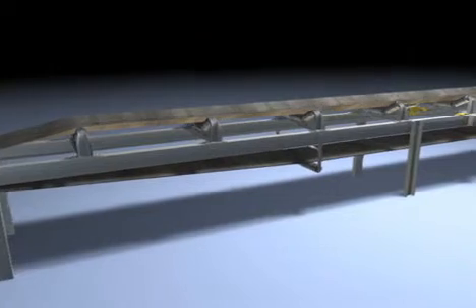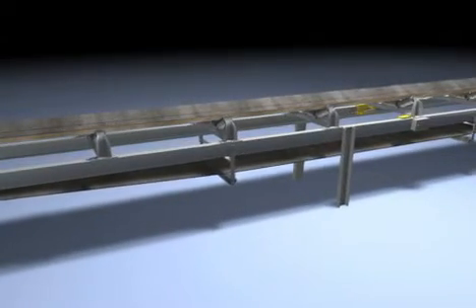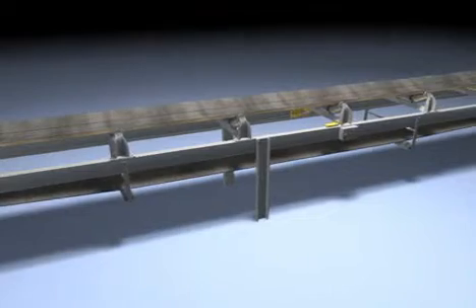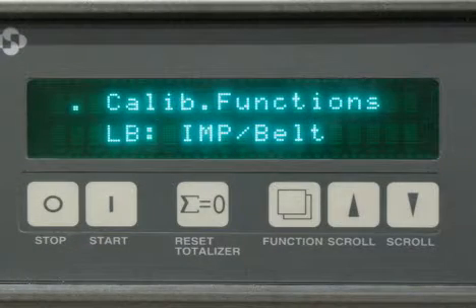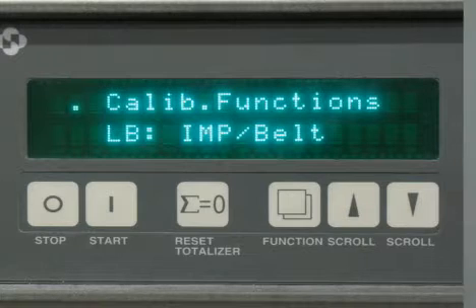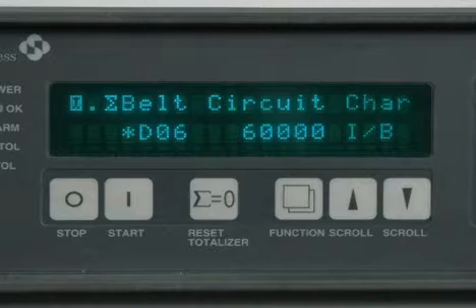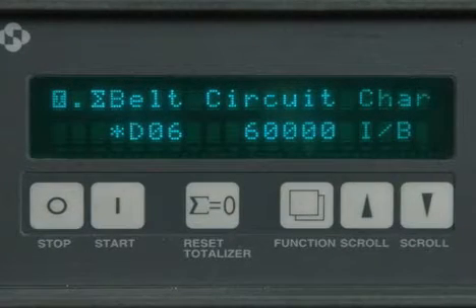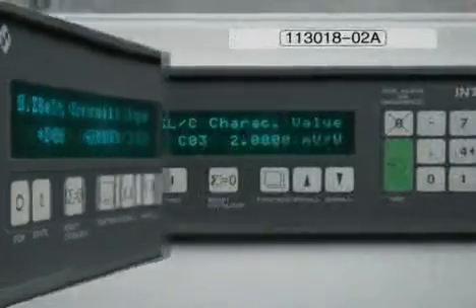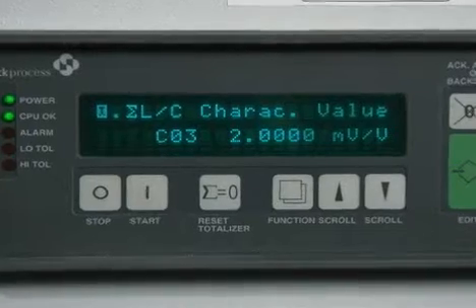The next step is to run the belt again, making sure to do so in volumetric mode at the same speed it was run previously. While the system is running, run the Impulses per Belt calibration program in the Calibration function menu. This program uses the value you placed in the belt circuit time parameter to count the impulses for 1 revolution of the belt. The BEMP software places the result of this test into the system as the belt circuit number. Check the value of this parameter. It should compare favorably with the impulses per belt number you calculated earlier. If it doesn't, check the calculations and correct any errors.